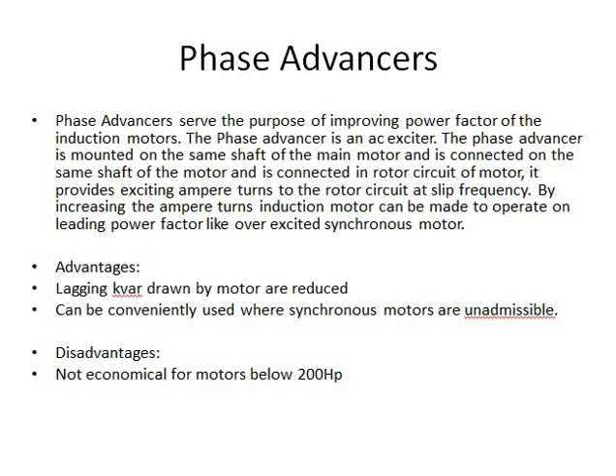The choice of selection also depends upon engineering and economic factors. They can be conveniently used where synchronous motors are inadmissible. Further, the lagging kVAr drawn by the motor is also reduced. And one of the drawbacks we can mention related to phase advancers is that they are not economical for motors below 200 HP.